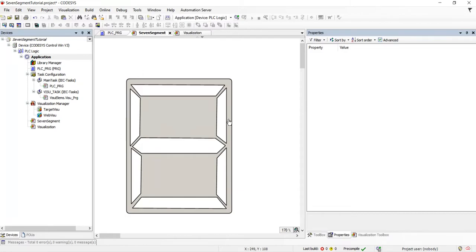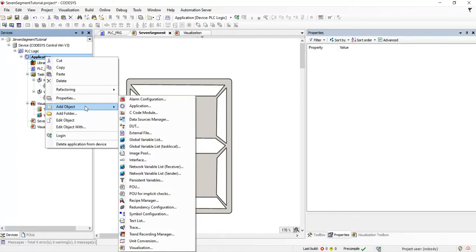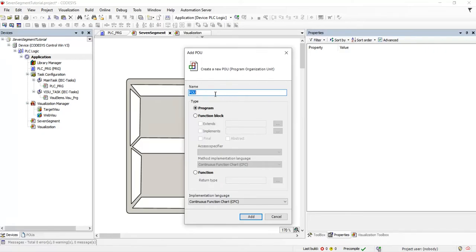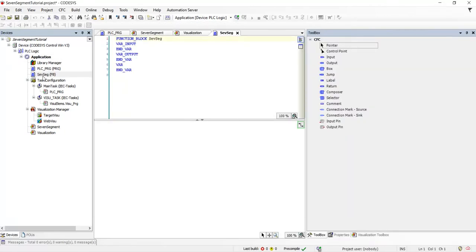Now that we have the seven segment created in the visualization, we need a corresponding function block because we are going to use multiple instances of this seven segment. For that we create a function block by right-clicking on the application, adding an object, and selecting POU (Program Organization Unit). Let's call it 'SevSeg' for short, as a function block using CFC as the programming language. We need to develop the piece of code which controls which segment should be turned on or off based on the decimal digit it receives. The function block needs one decimal integer input as a single digit.